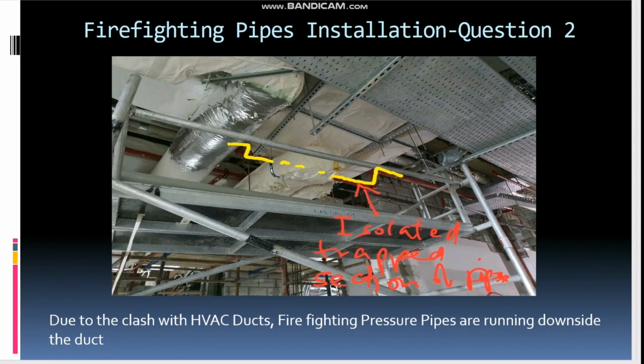And the second question here is, if you see here, the firefighting pipes are coming from here and going down, and again it's going up because here there is a duct passing, HVAC ducts are passing like this. So we cannot take the pipe straight away like this. So the arrangement is going down, again here going up. Firefighting pipes, as you know, it's a pressurized system. It's not a sewerage, it's not a rainwater pipe, it's not a gravity pipe. So we have a pressurized system in the firefighting.